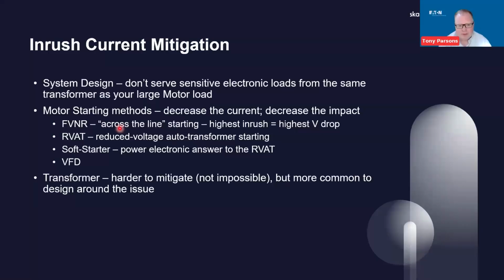As far as dealing with these inrush currents, a big part of it, and I know Steve has seen the same things when he's done surveys, is just proper system design. If you have sensitive electronic loads, don't feed those from the same transformer as your large motor loads that may be starting several times a day and creating voltage sags. Or don't feed your PLC control equipment that's controlling your whole process from the same panel that your welders are fed from, right? You're mixing sensitive loads and polluting loads.